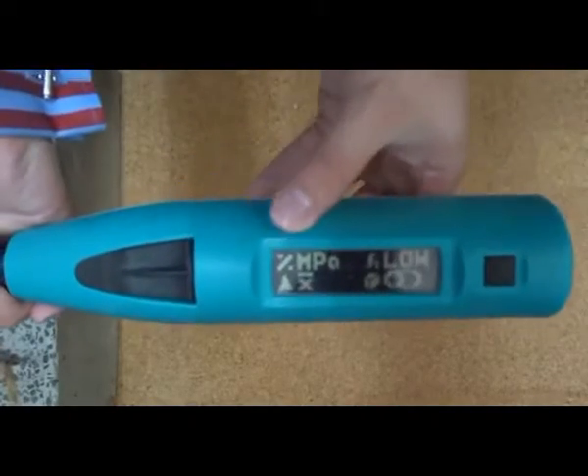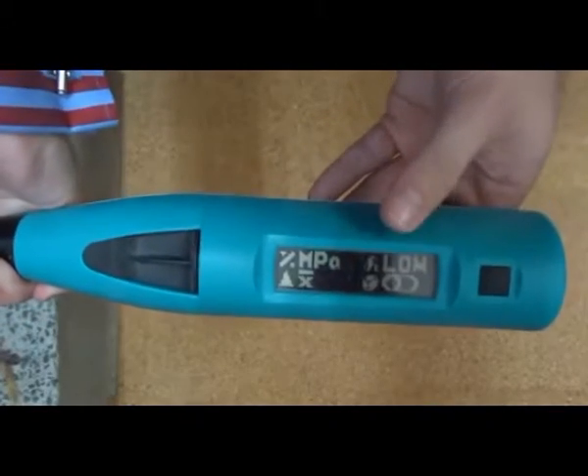We can check the settings in the hammer by depressing the plunger slightly. And as you can see, we've set it to MPa for the unit, a cylinder, the lowest 10th percentile curve, and an averaging method. We're now ready to take the measurement.